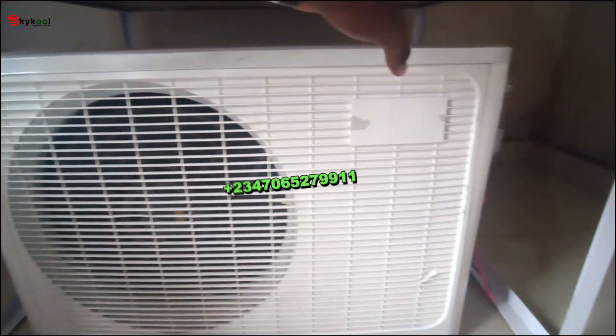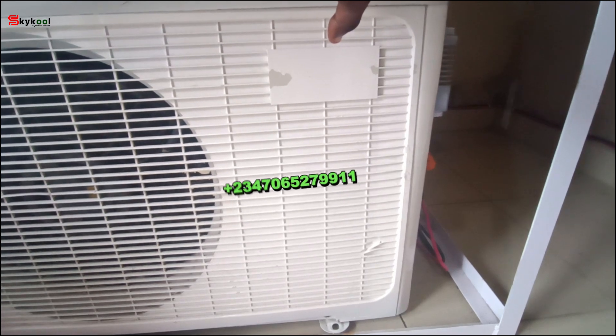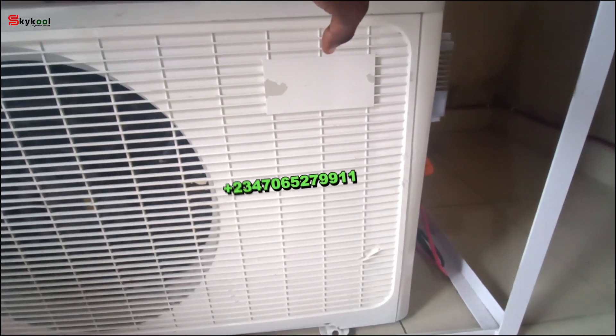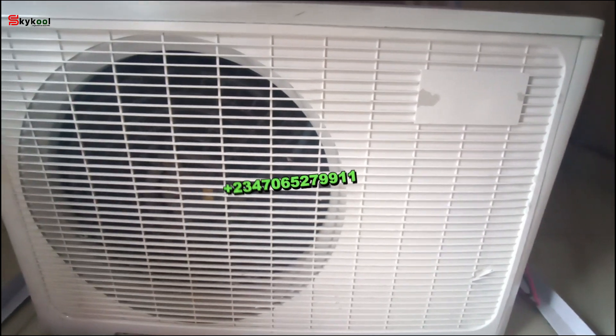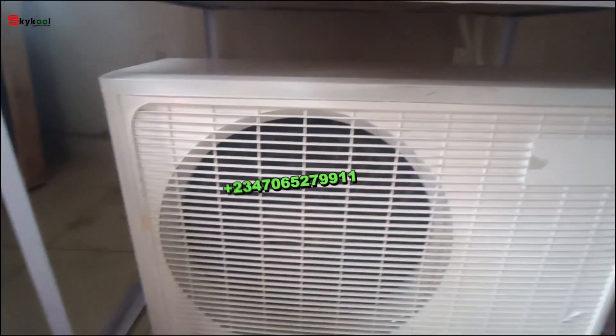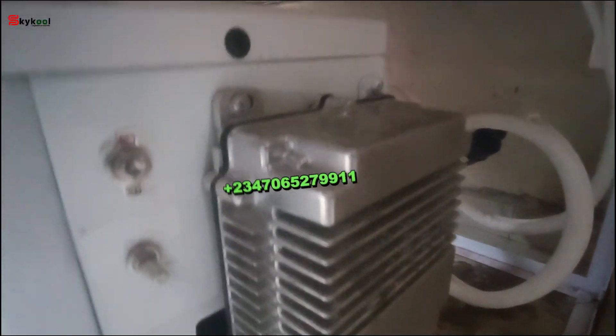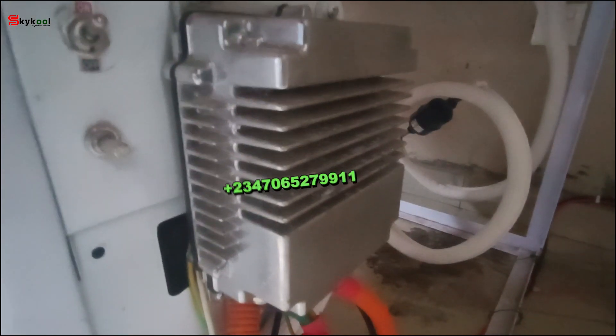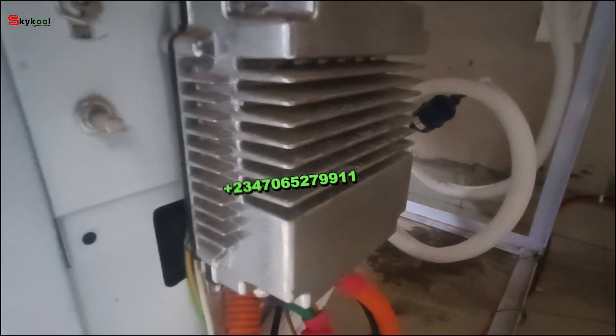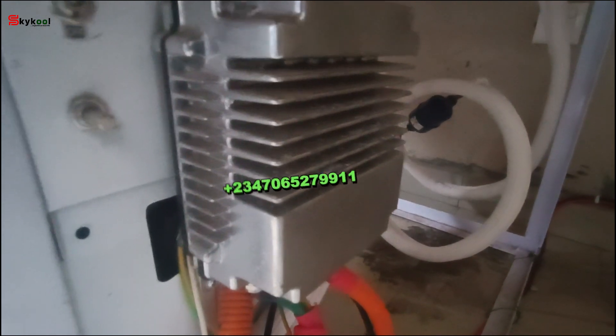Underneath — small but mighty — a 1.5-horsepower condensing unit equipped with a 1.5-horsepower 48-volt DC compressor that changes the dynamics of this entire system. The condenser keeps working continuously while connected to battery direct. Here is the controller of the compressor connected directly to the 10-kilowatt lithium battery — no inverter needed, no electricity.